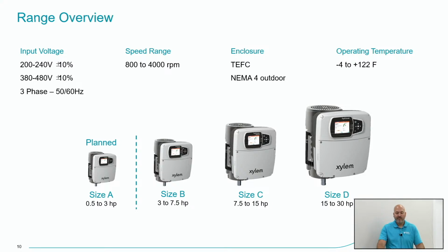We do have our first question, which is to clarify: did I hear correctly that you can use single phase 230 volt input? No, strictly 3-phase input for the Hydrovar X products. The single phase offering would be the size A, which accepts single phase or 3-phase from 1/2 to 3 horsepower, but that is a different product as it stands today. So if we're specifically talking Hydrovar X from 4 to 30 horsepower, it's 3-phase input power only.